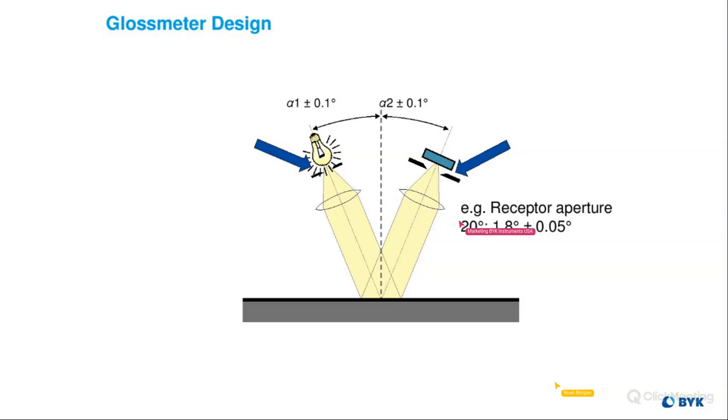So typically, a matte surface has very low gloss. And what you can think of happening in a matte surface is a lot of microtexture. Because of that microtexture, colors might seem a little dull, versus if you had a high gloss surface, you would say that the colors look very brilliant, very bright. So really, gloss is one part of a multi-part process to figure out what the color is, if that makes sense. I would say gloss has a very big role on color evaluation.